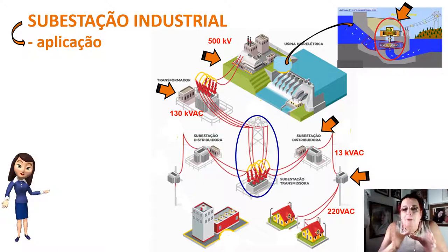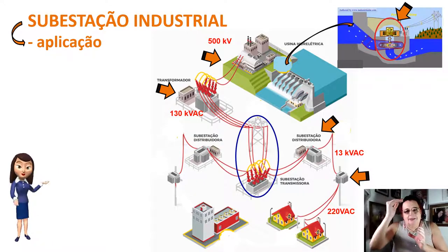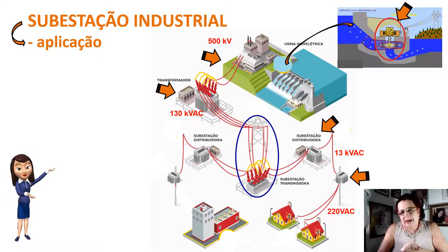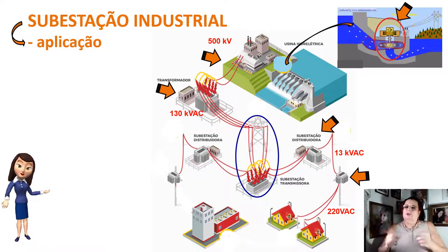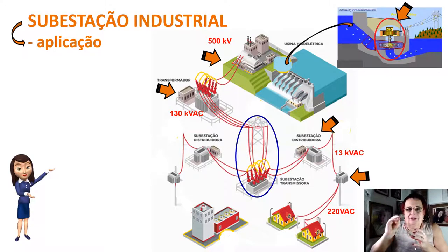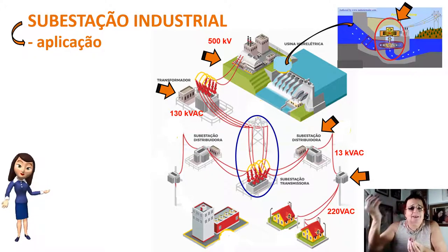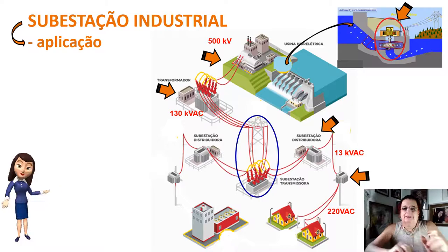No poste existe um transformador que rebaixa de 13 mil para 220 volts para alimentar a sua casa. Se a sua casa é 110 volts, é porque entra uma fase de 220 volts alimentada com um neutro e, na condição fase-neutro, gera 110 volts. Mas entra 220 volts na sua casa.